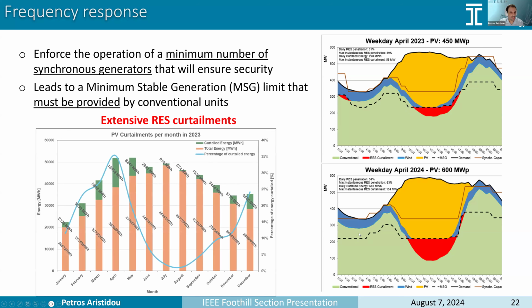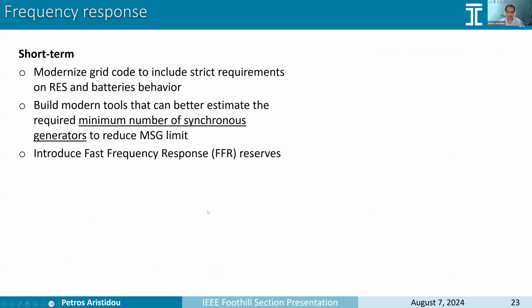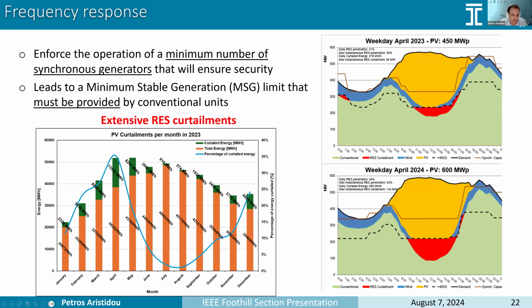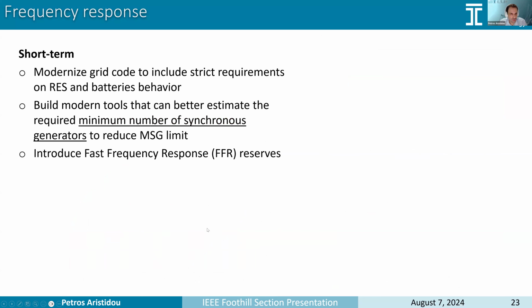We see that the amount of curtailment has increased. And actually, we can see here a little bit in this schematic how this curtailment behaved. In the worst case scenario, in April, we had to curtail 35% of the renewable generation. So 35% of the renewable generation was curtailed and thrown away, while in 2024, this has reached 40%. Now, how can we change this? Because we don't like it. We don't like to do RES curtailments.